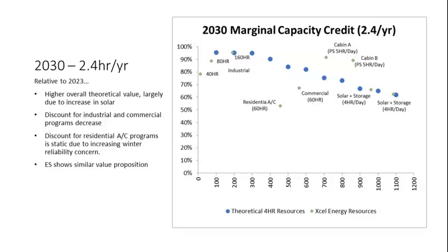That provides a particular loss of load probability 8760 strip, and then each one of these resources is dispatched against that, each time maintaining that reliability standard of either 0.1 per year or 2.4 hours per year metrics. So the dispatch algorithm isn't on price, it isn't on load or net load, it's on LOLP, and that LOLP, of course, is shifting and changing with each dispatch of that resource. So the first one's dispatched, and that changes that profile. The second one's dispatched, it changes this profile. And even within each of these categories, it dispatches in 25 megawatt increments until it gets up to the full capacity of energy limited resources here that we have at 1100. So it's trying to maintain a fair evaluation based on a single minimized LOLP metric.